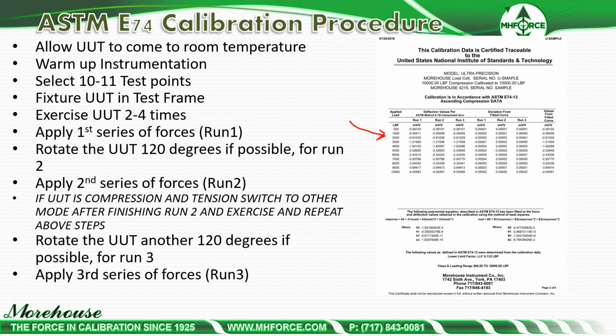Rotate the UUT 120 degrees if possible for run 2. If it's tension and compression, you're going to want to start with one mode, probably compression, switch to tension, run all of your tension cal, 0 degrees, 120, 240, and then switch back to compression. So that's what's going on here. We're doing that when we talk about deviations.